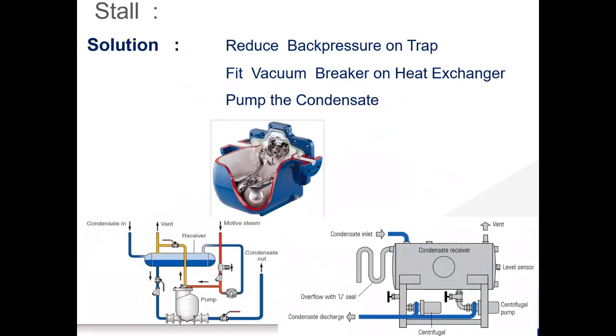So how can we clear that? We can use an APT, an automatic pump solution. What this does is reduce the back pressure on the trap. You fit vacuum breakers after the control valves to allow air in, so you're not pulling a vacuum. Although we would recommend other solutions before that.